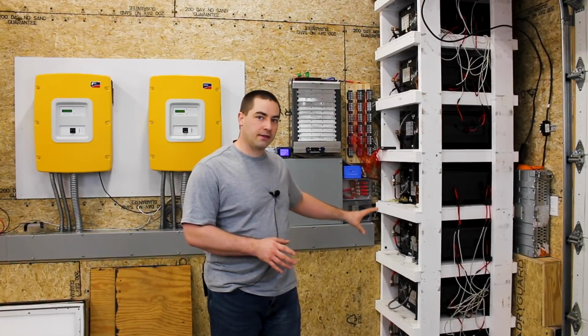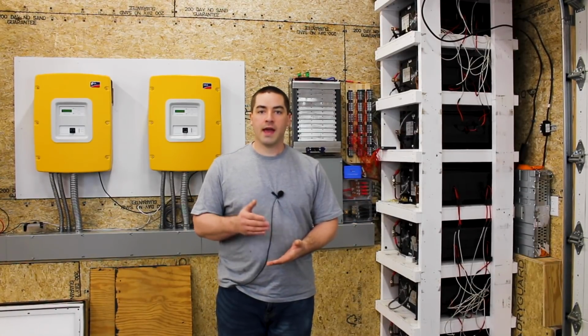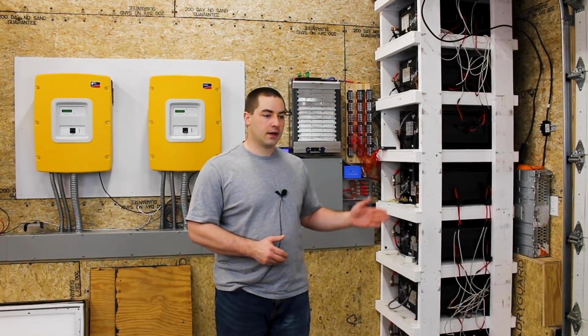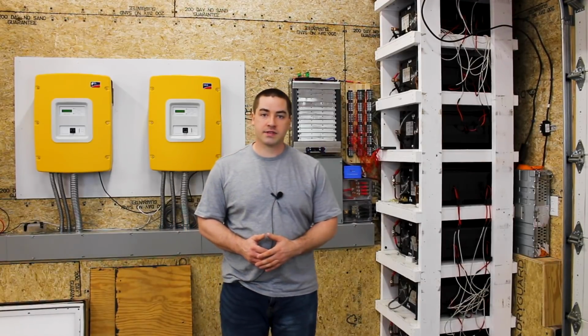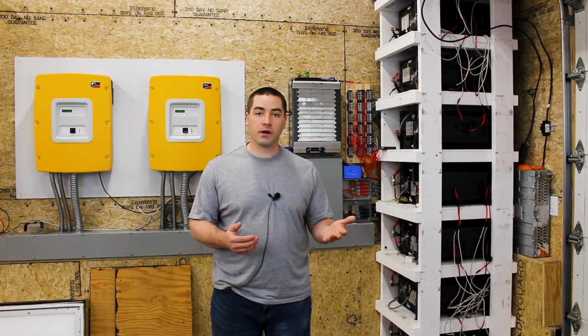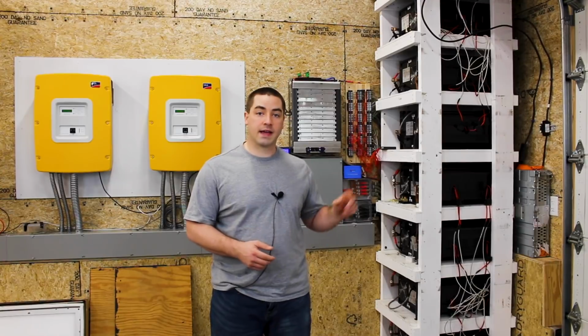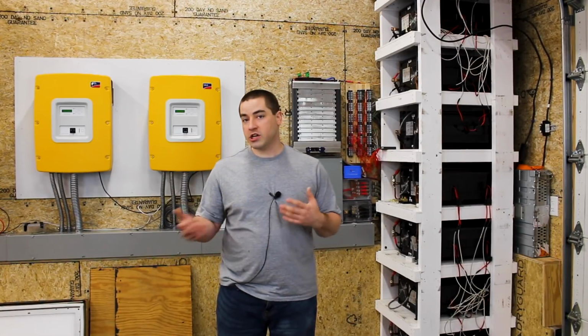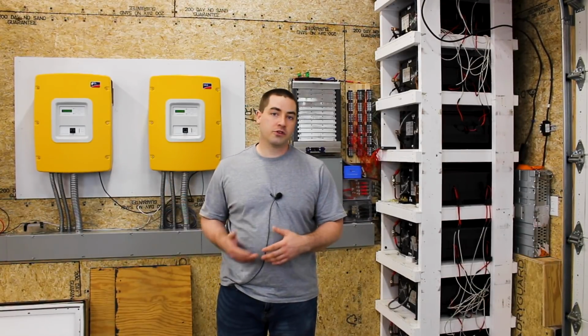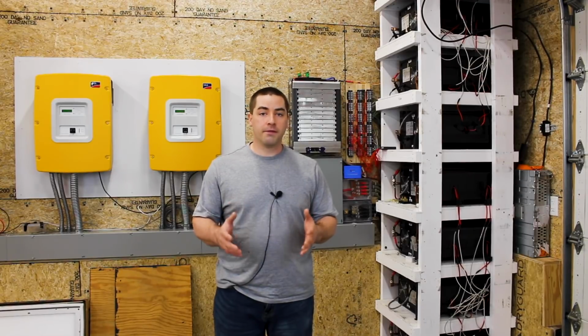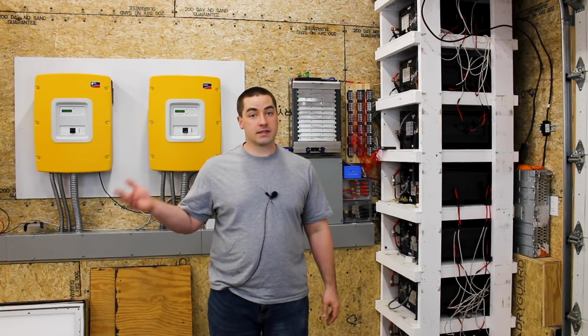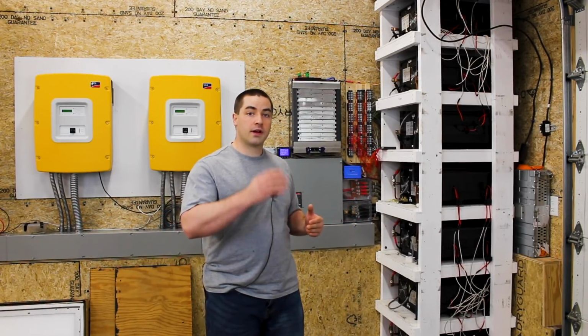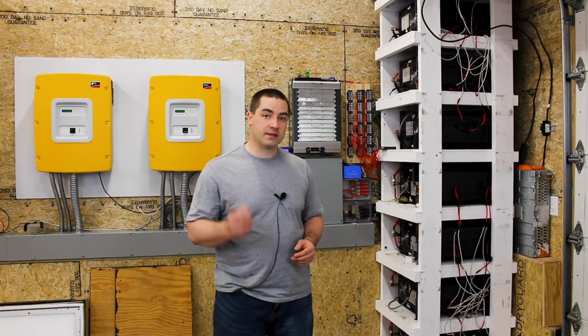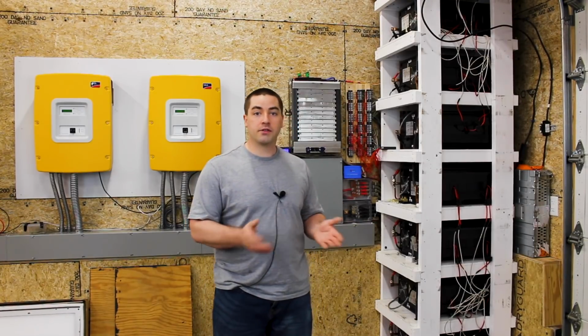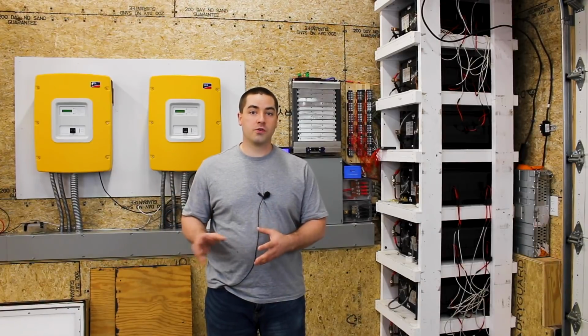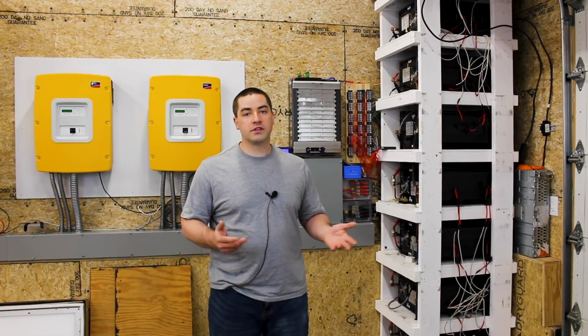Drain the whole battery bank down. Now I will stop it at 48 volts, and that's the cutoff that I have set in the BMS. I want a consistent load so that as I add batteries in the future, or I change things up, or change the inverters, or whatever I decide to do, if I want to do another capacity test at some point, I can turn on the exact same water heater, have the exact same load, and compare the two with those controls in place. I don't want all these variables.